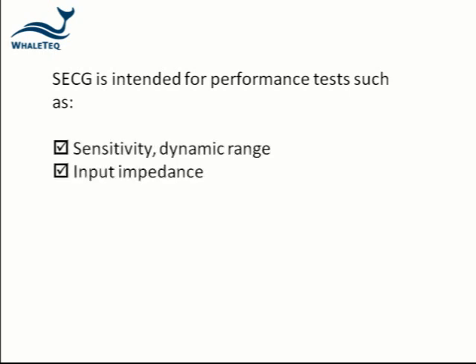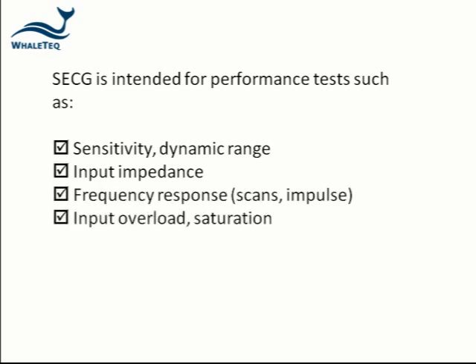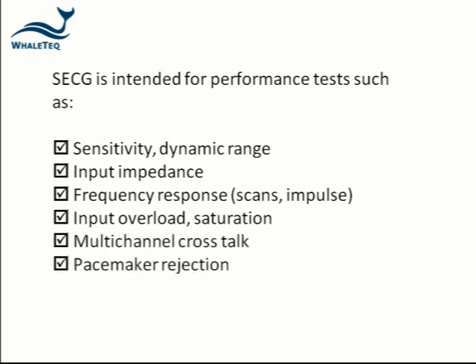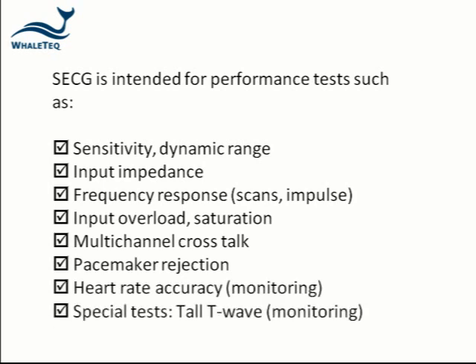The equipment is intended for performance tests such as sensitivity and dynamic range, input impedance, frequency response using scans and impulse tests, input overload and saturation, multi-channel crosstalk, pacemaker rejection, heart rate accuracy, and special tests such as tall T-wave rejection, baseline drift, and minimum response.